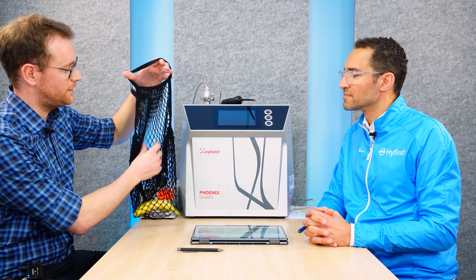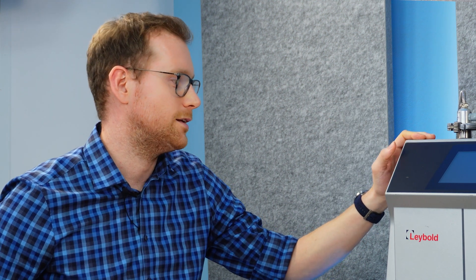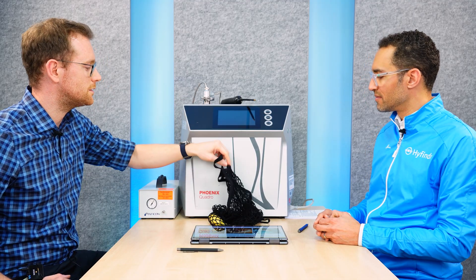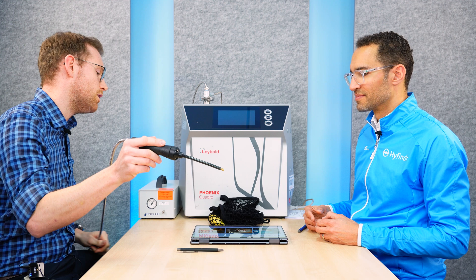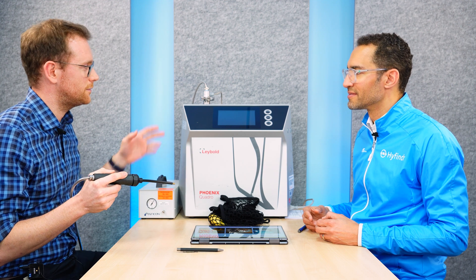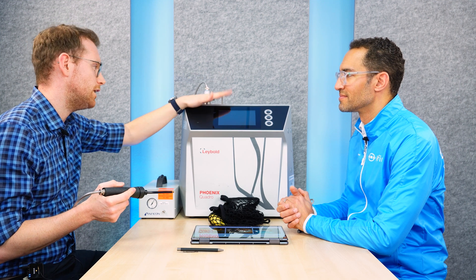For very small leaks — tens of microns, for example — you will usually use a helium leak detector that you can run with either helium or directly with hydrogen. It's basically comparable with a hoover. We have a sniffing line that you use and you go along your whole pipe, and it's sucking in every piece of air that it gets. Inside the machine is a mass spectrometer, which is basically a machine for counting hydrogen or helium atoms.